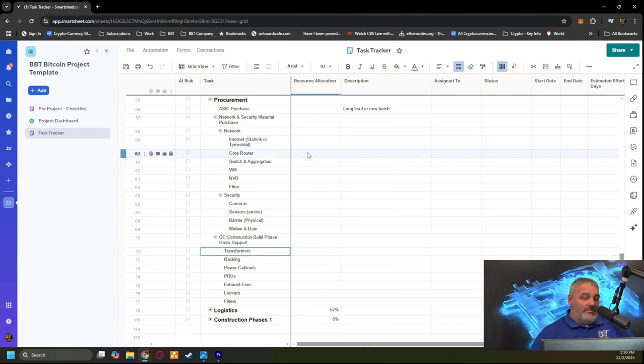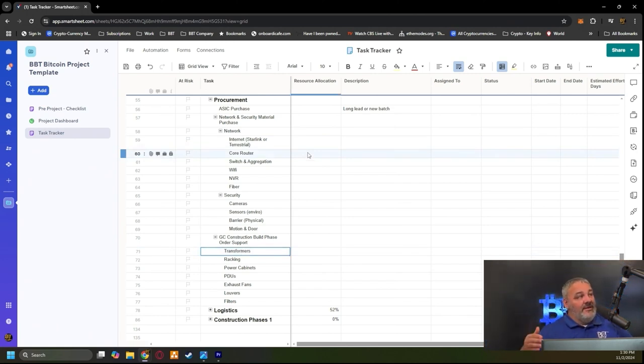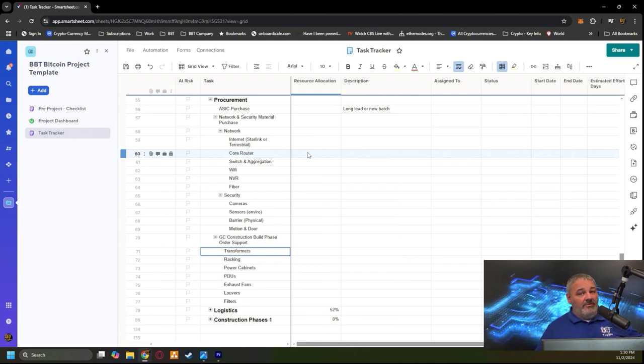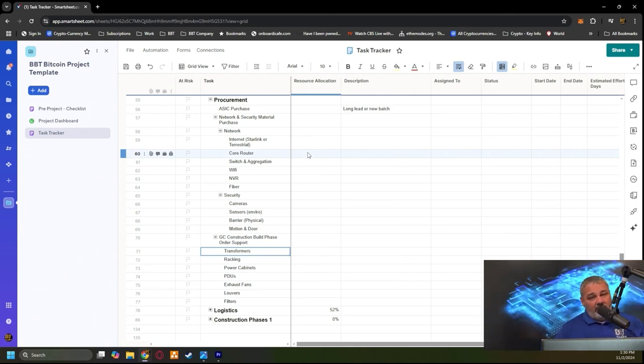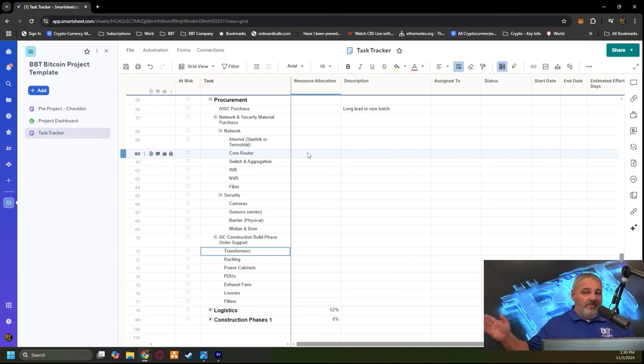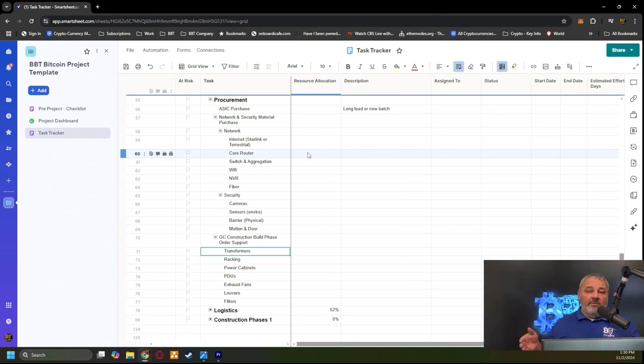Is the power company providing you the transformers, what kind are they? You're going to need those secondary connections for the electricians. What are the setbacks for those? What kind of racking are you going to use? Are you building something internally? Is there power cabinets that already have the breakers built in for the sub breakers? Are you going to use PDUs down to each spot with breakers built in? What's your points of disconnect and your points of fault tolerance?